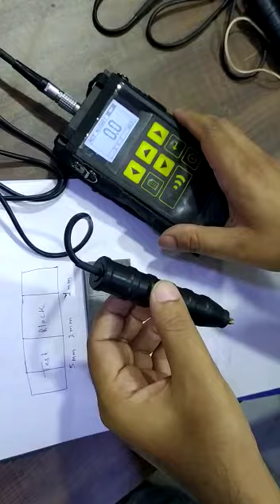This is the crack depth gauge machine. This machine is used to measure the depth of surface cracks. I have connected the probe with the machine. Now I will select the material.